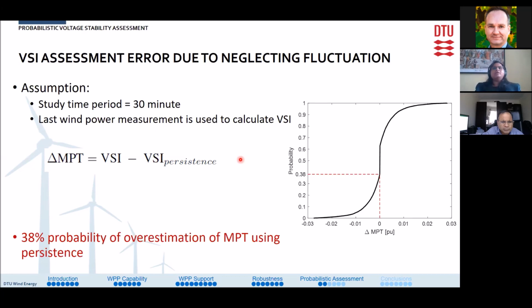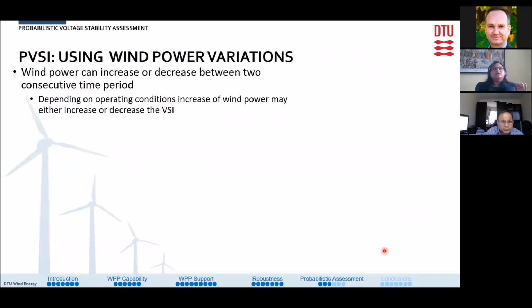When we do the error analysis, we see from the cumulative distribution of error here that there is a 38% probability of overestimating the voltage stability index if using the index based on persistence. So this led to the development of two methodologies for calculating the probabilistic voltage stability index. The first one uses the variations in wind power. Wind power can increase or decrease between two consecutive time periods, and depending on the conditions, the increase in wind power may either increase or decrease the voltage stability index.